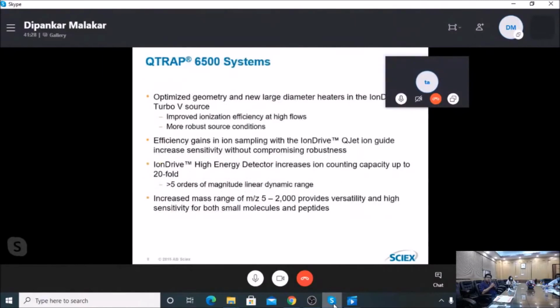Now coming to the Q-Trap 6500 system, what is the specialty in this system? This optimized geometry and new large diameter heaters in the ion drive source, the Turbo V source, actually improve the ionization efficiency at higher flow rates.